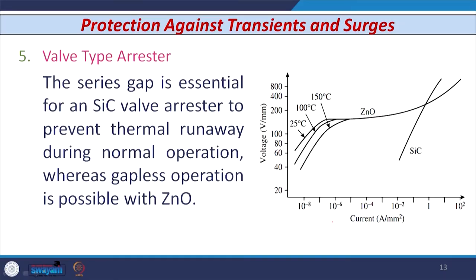Comparing the characteristics of silicon carbide and ZnO type arresters plotted as voltage (V/mm) versus current (A/mm²): the silicon carbide arrester shows increasing voltage as current increases. In contrast, for the ZnO type, even as current increases significantly, the voltage remains almost constant. This is why in practical applications, the ZnO type lightning arrester is widely used.